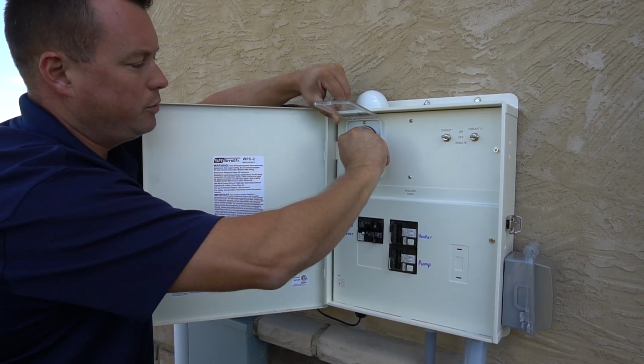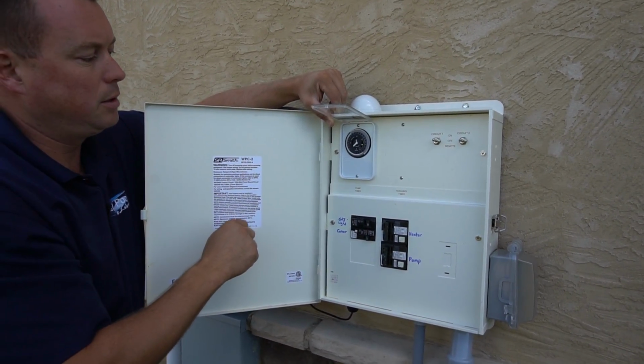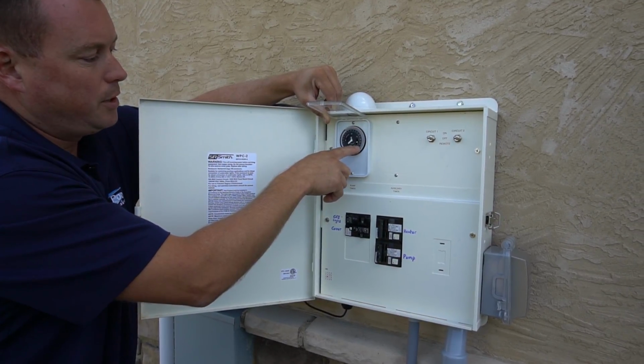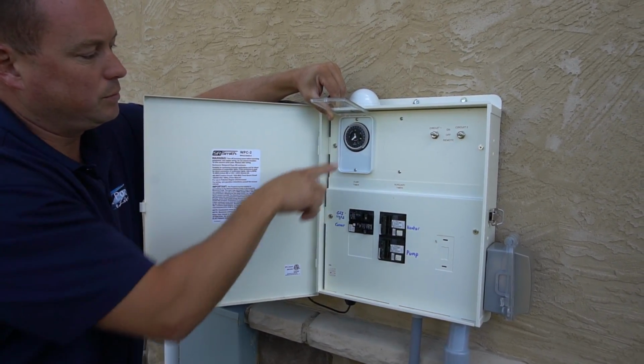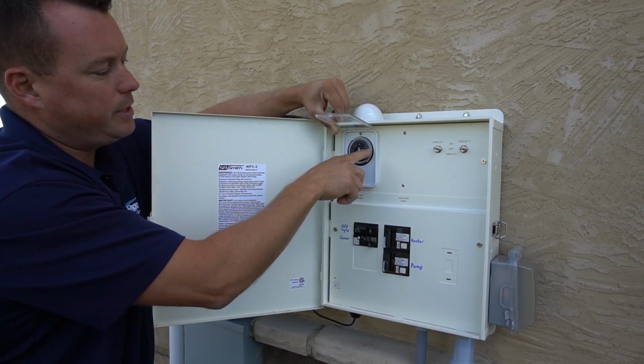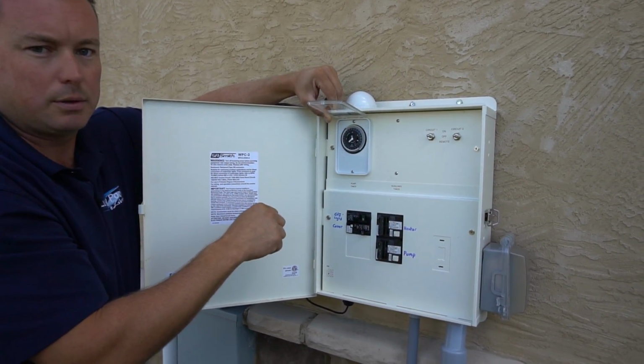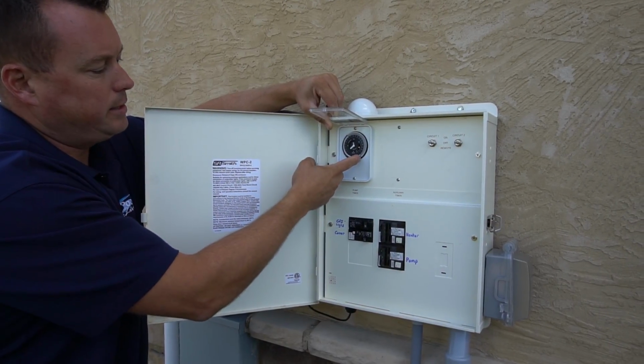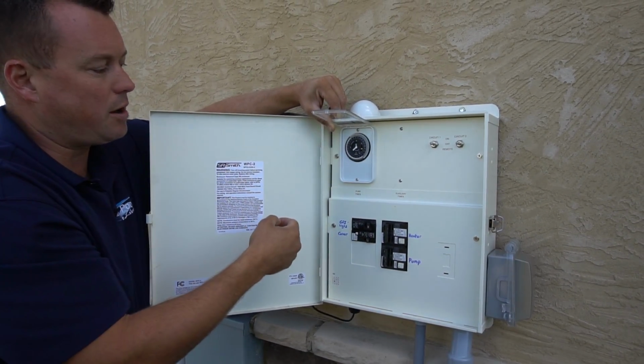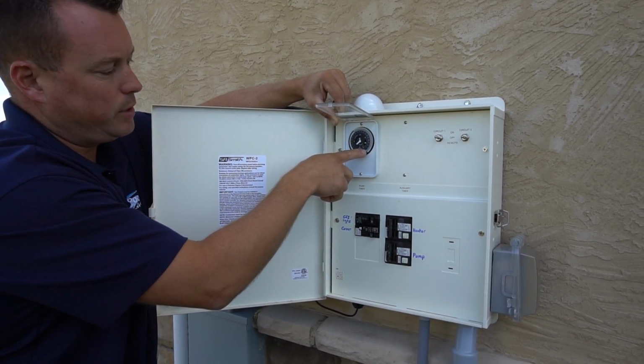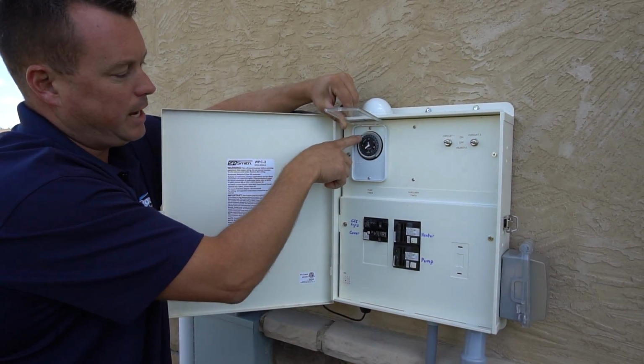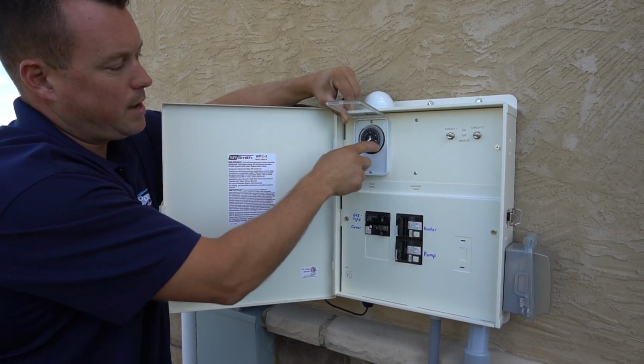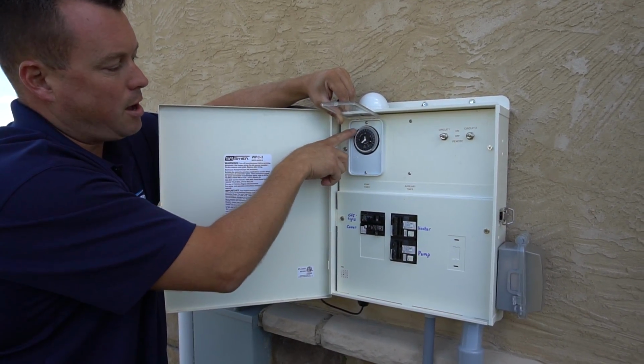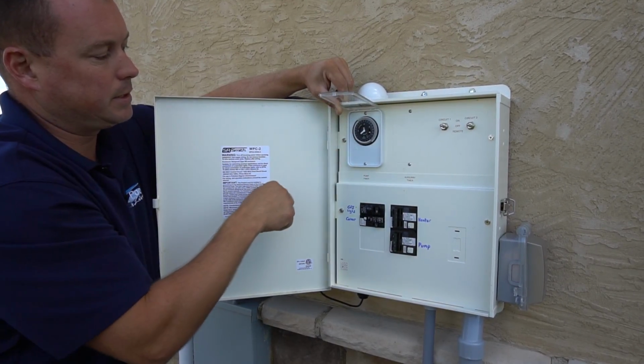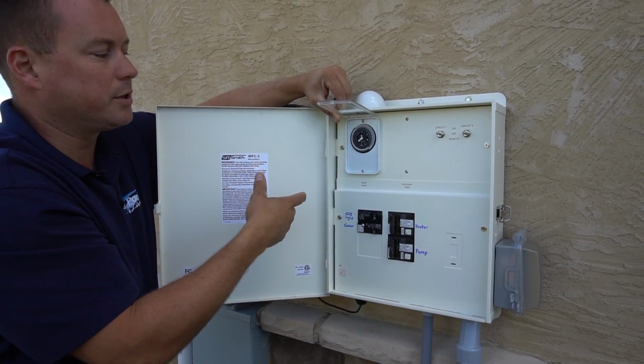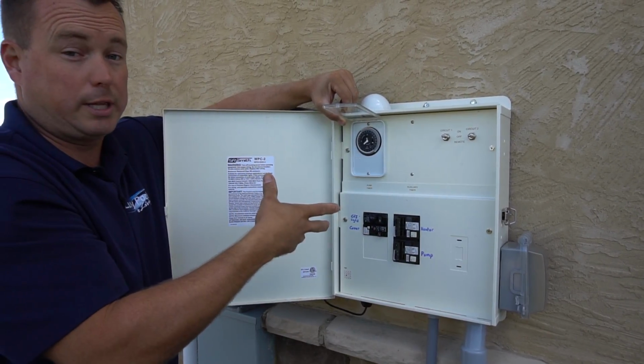So if we move our switch to the middle, our pump is going to follow the schedule. And right now it's just about noon. Current time is here. Any of these tabs that are pushed out is in an on position. Any tab that's pushed in is an off position. So in this case, we have from 6 a.m. to 1800, 6 p.m., we have our pump running, and then off from 6 p.m. to 6 a.m.